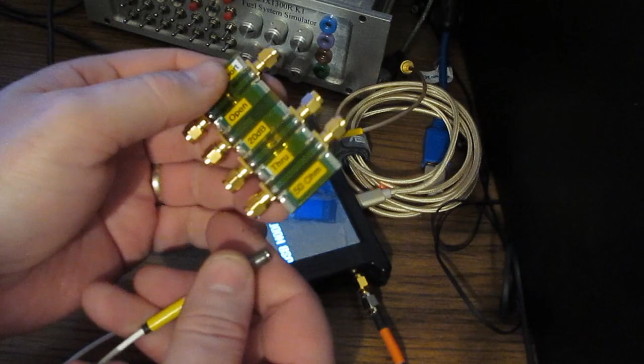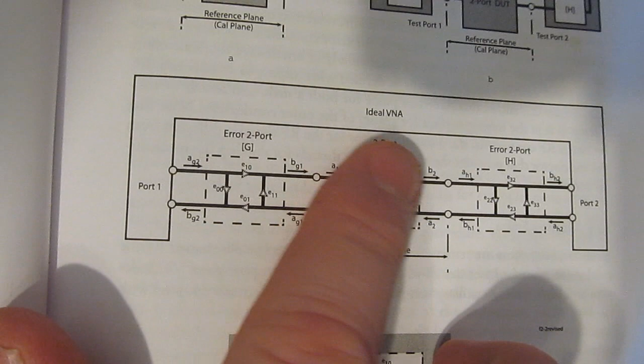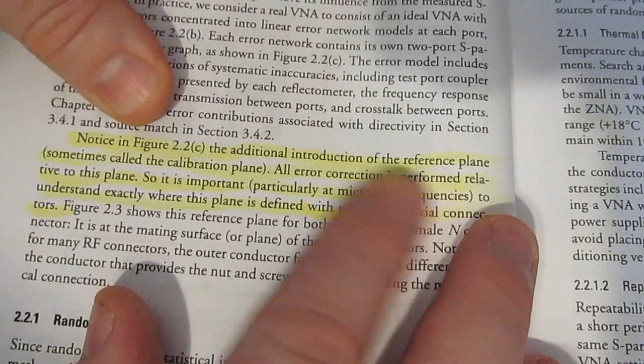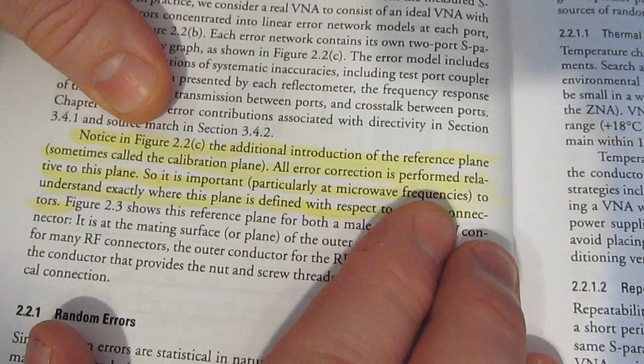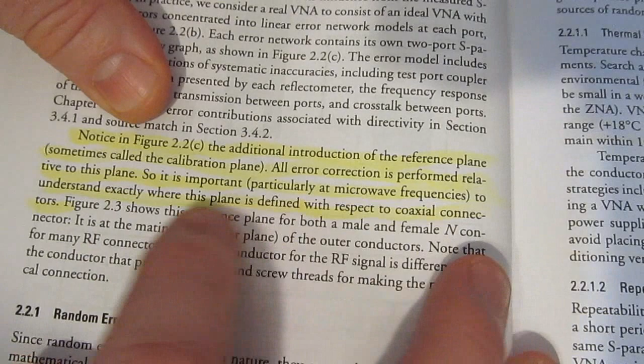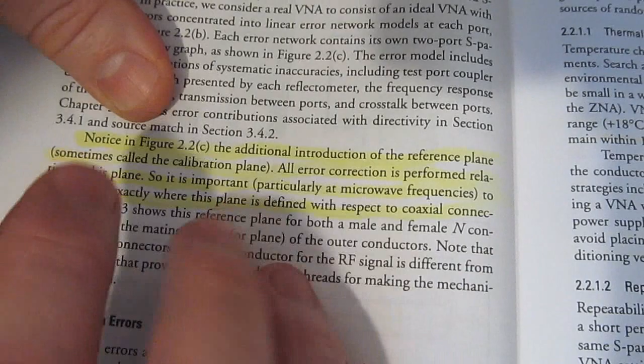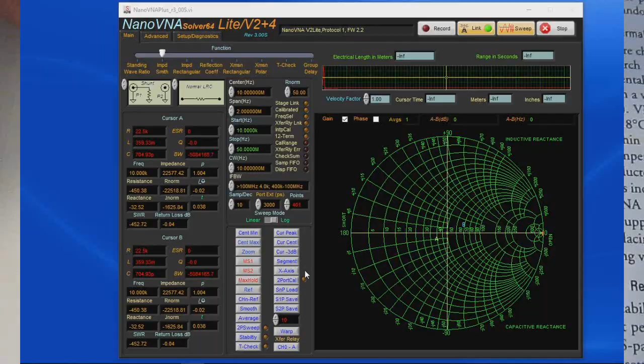Again, the whole idea of this port extension is that we can make adjustments for where we've set our reference plane. Of course, for our homemade standards, our reference plane would be at the end of the open, for example. 2.2, where we're looking at measurement errors in the real world. Here they show the ideal model for VNA. Notice they're referring to the reference plane or the calibration plane. So notice in figure 2.2c, the additional introduction of the reference plane, sometimes called the calibration plane. All error correction is performed relative to this plane. So it is important, particularly in microwave frequencies, to understand exactly where this plane is defined with respect to the coaxial connectors. Again, what we're doing with these error models is we're compensating for every error that's in front of the reference plane, not beyond it.